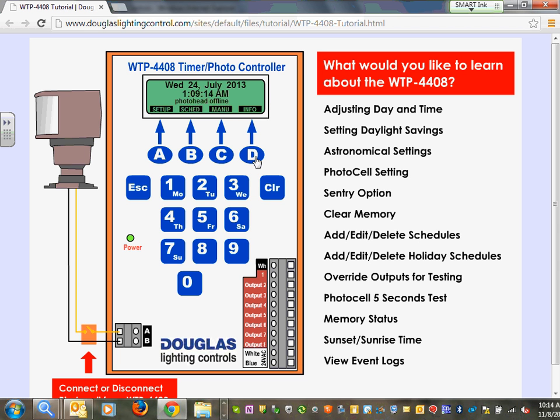Yep. Okay. And so that little card back there happens to be LON space, right? So any LON manufacturer can tie into the data line at that port, and if they're a LON certified manufacturer, they can tie onto that, and they instantly know everything that's going on downstream. If they're not LON and they're BACnet, there's a different device that we use, and if they're not LON or BACnet, then we have gateways to deal with it. So it could have been a Honeywell system or a Johnson Controls system or whoever.